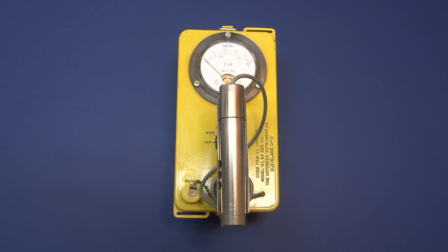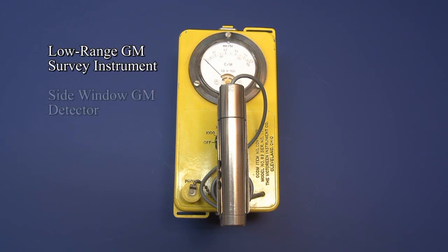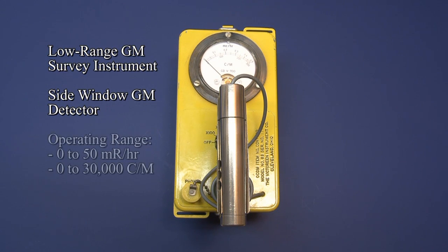This is a sensitive low-range survey instrument that employs a side window GM or Geiger-Mueller detector. The instrument gives an overall operating range of from 0 to 50 MR per hour, or 0 to 30,000 counts per minute.